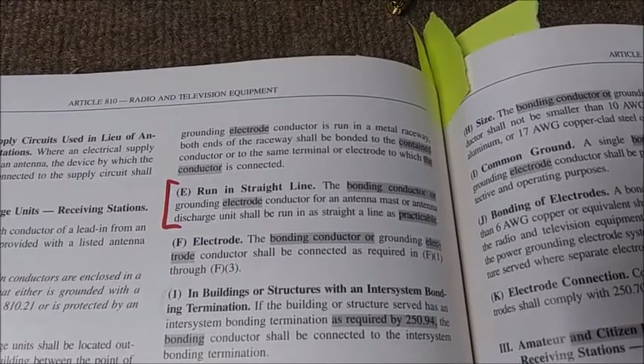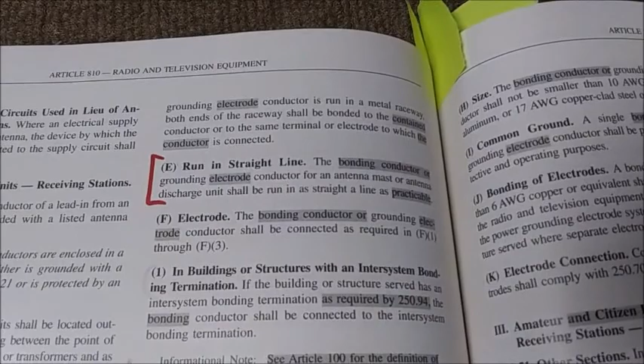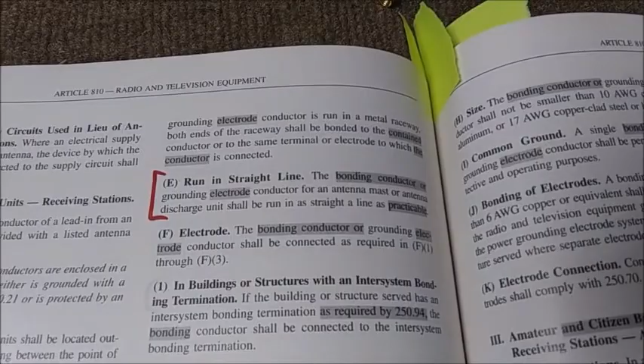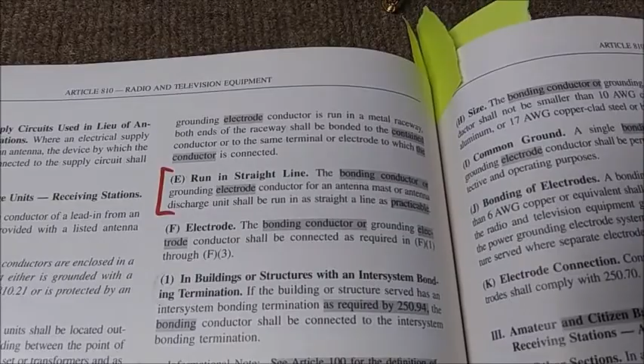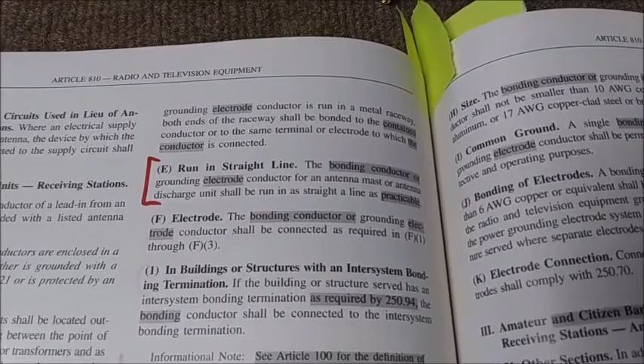Run in a straight line. This is a critical point. I bought an old house here. I found that the number 6 ground wire from the conduit down to the meter box was underneath the concrete thing that catches the gutter water. That's a universal sign that somebody tried to hide the fact there's no ground rod. Because if there's a ground rod, that concrete thing won't fit over it. I pulled the concrete thing away. Sure enough, somebody had stuck the wire down in the dirt. So I put a ground rod in.